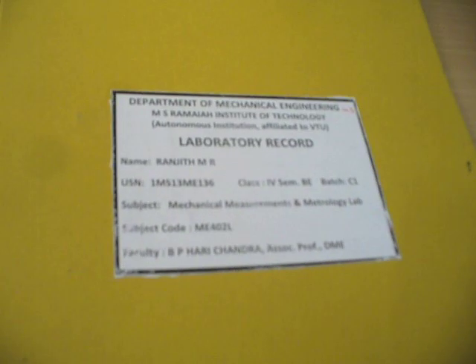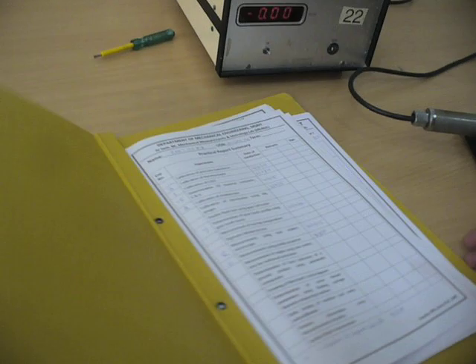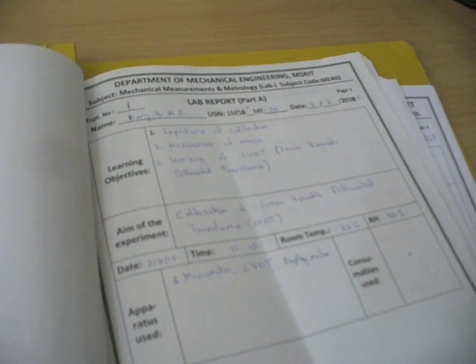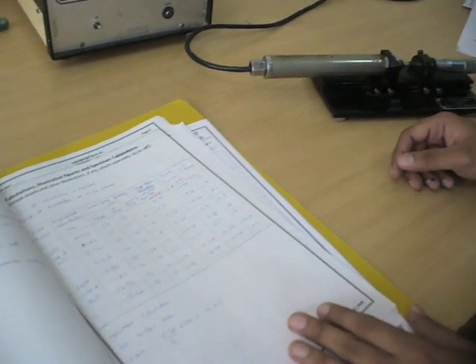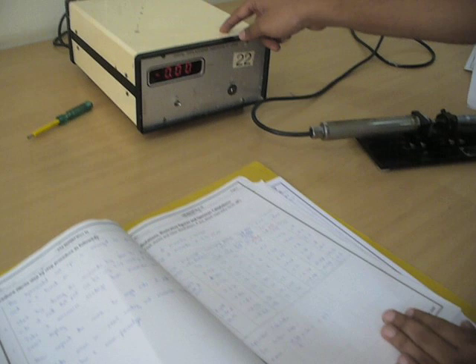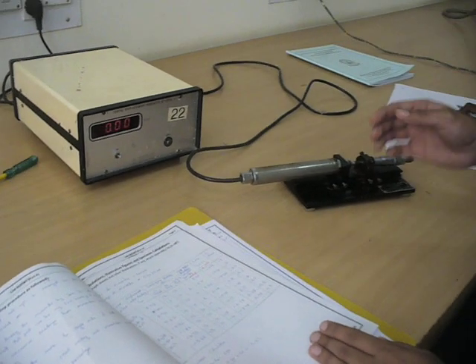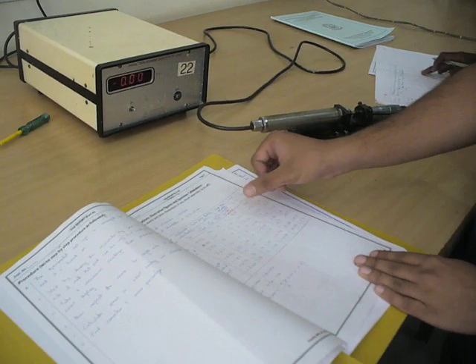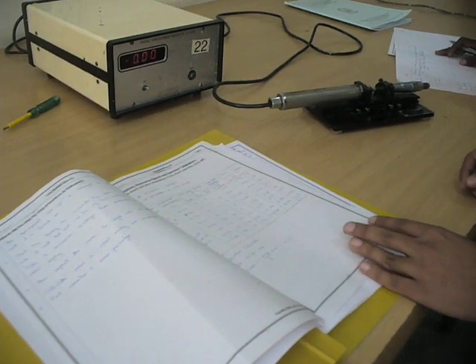So we'll go to the observation table. We have mainly three learning objectives: the importance of the calibration, the measurement of error, and how the LVDT works. And this is our observation table. We have the core position, which is to the left side of null and to the right side of the null, as there are two secondary coils. We have the displacement meter reading, which is the screw gauge reading, our standard, and our correction and error. So we'll start off.